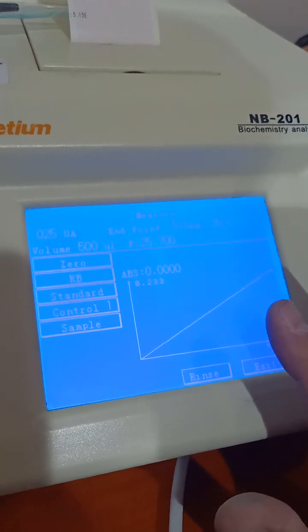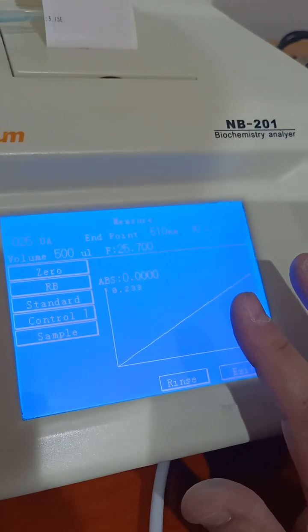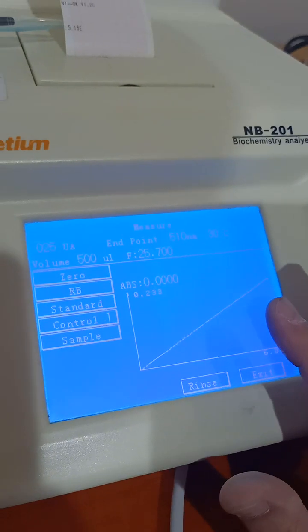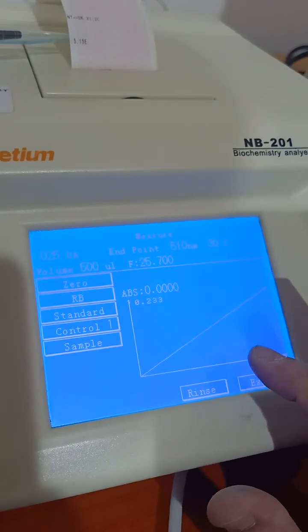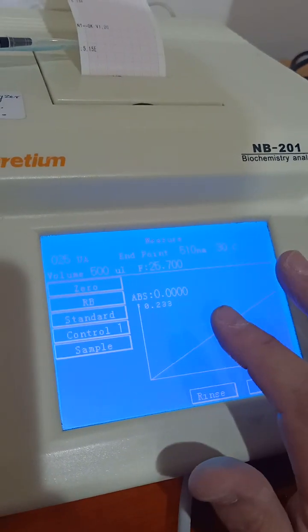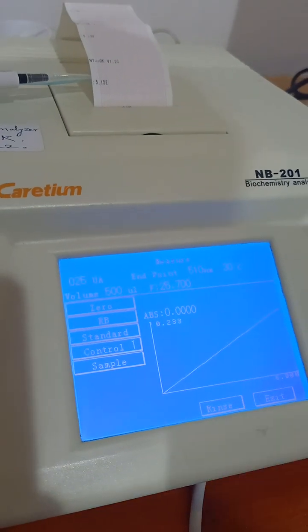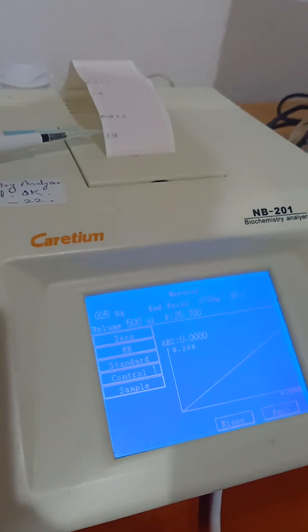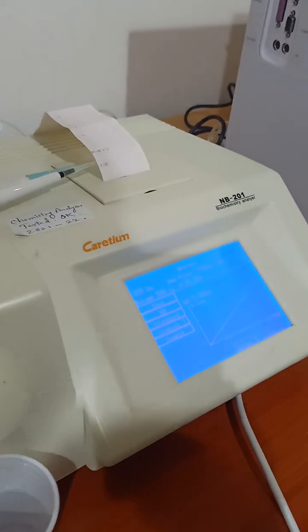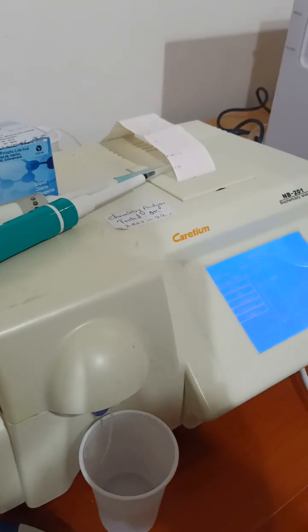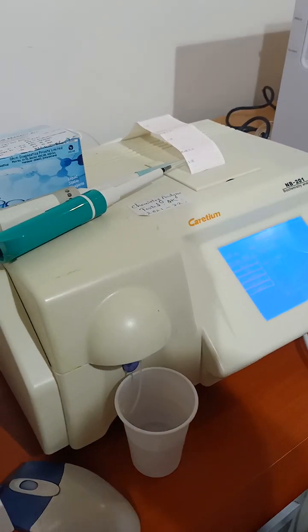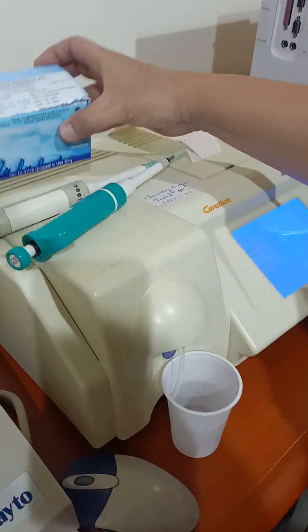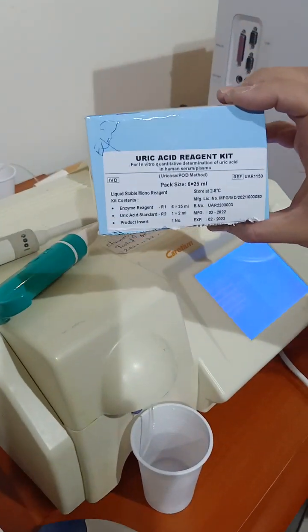Now we will check one test of these parameters already installed in this spectrometer. So we will make analysis for uric acid in blood. There is a reagent kit here. We use it.